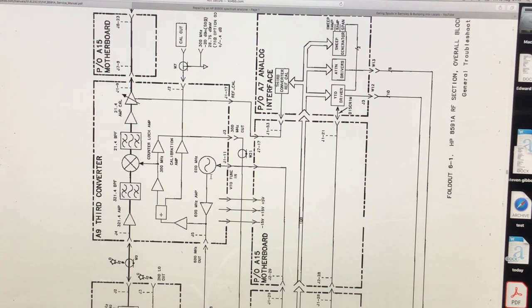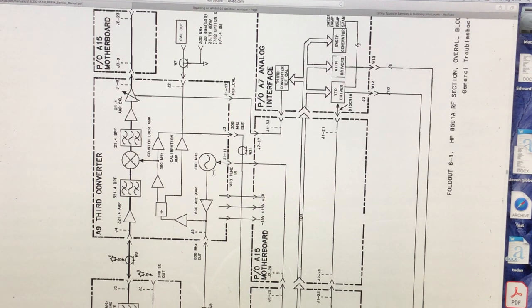So this still could have an issue, because it did look like as if when we fed the signal in from the signal generator into the front of the instrument to start with, it was off frequency. So it could still be an issue in this area, and the calibration amp or the oscillator itself could be an issue. So we've got J1-11 there, which looks like as if that's the input to the tuned oscillator.